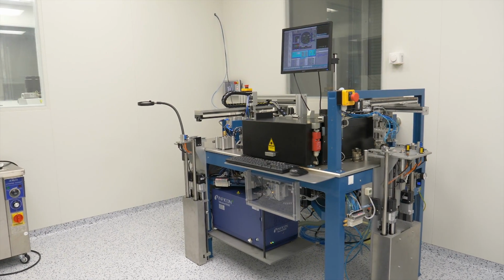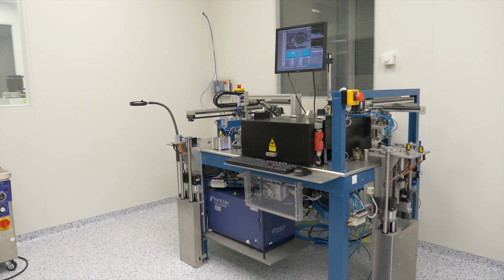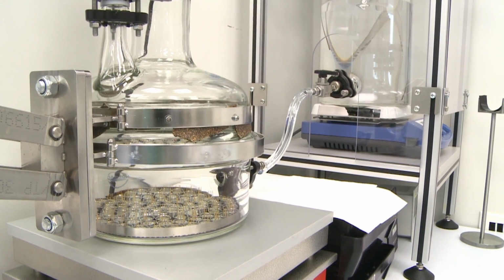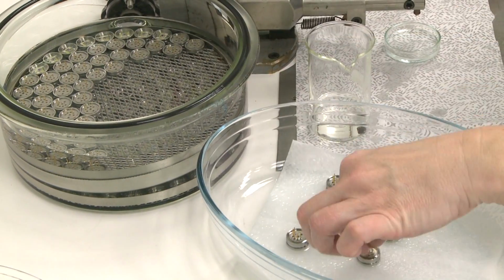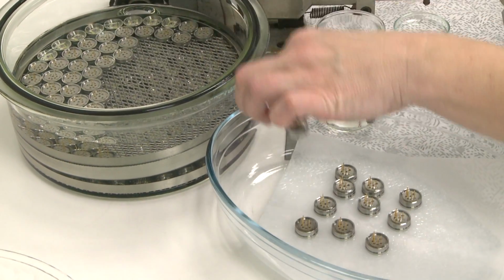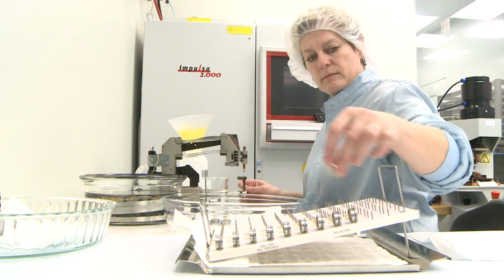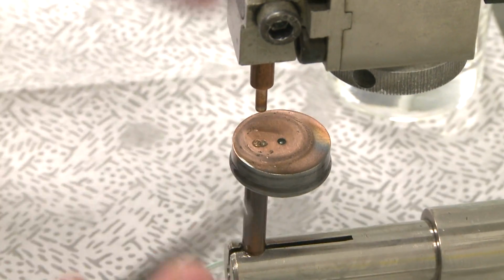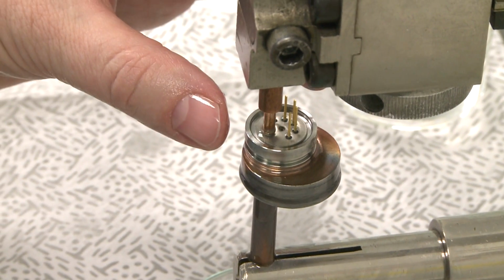In order to transfer pressure from the stainless sensor's diaphragm to the chip diaphragm, the inner space in the vacuum is filled with inert oil. The sensor's inner space is then closed by a ball, which is welded to the base using a current impulse.